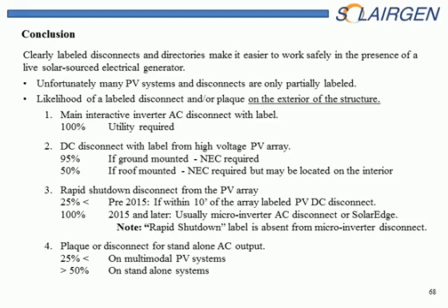The rapid shutdown disconnect. Well, this is a new requirement, after 2015, where they require this on high voltage inverters. So before that time, probably 25% of the time the disconnect was actually outside and within 10 feet of the PV array. Probably less than that. So there is a potential for the old string inverter with high voltage and no disconnect within sight. There is a possibility of that. Plaque or disconnect for a standalone AC output. Multimodal systems, honestly, probably less than 25% are actually on the outside of the structure. Standalone systems, more than 50%. I would say it'd be closer to 100%, but it kind of depends on whether it's a cabin or whether it's an actual home as to whether it would have that.